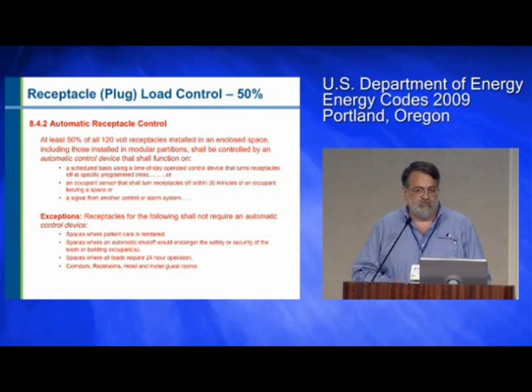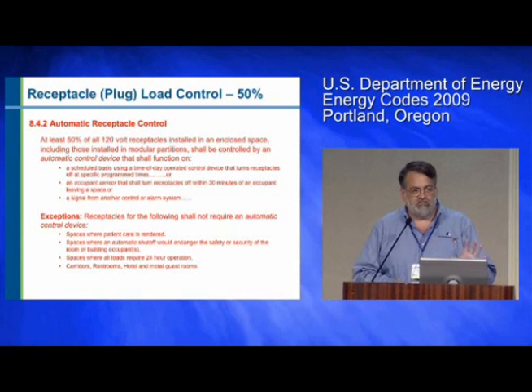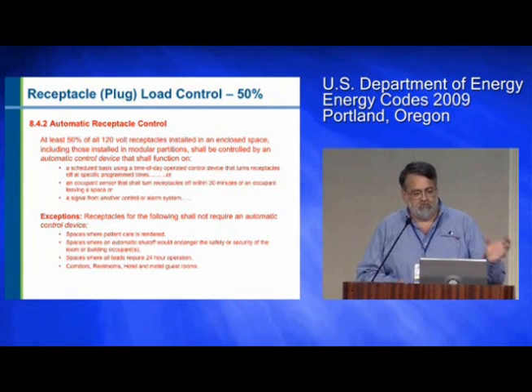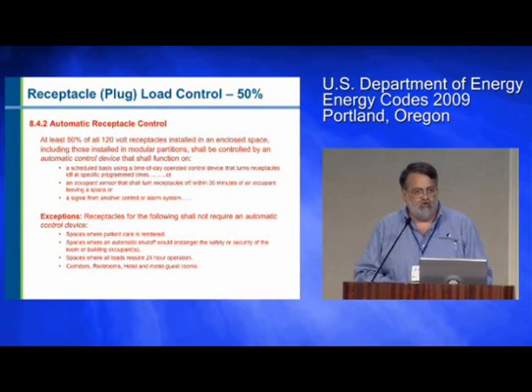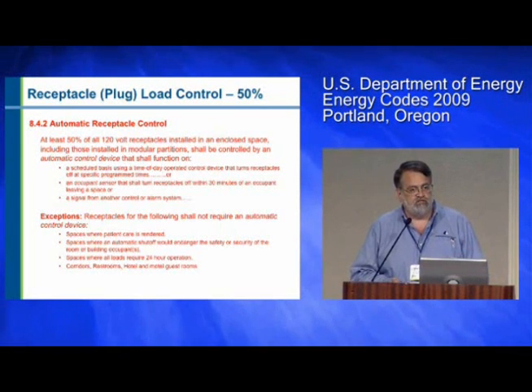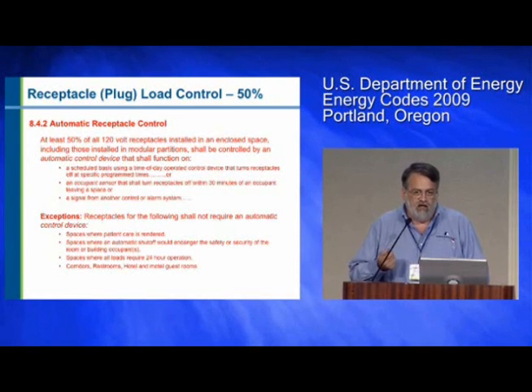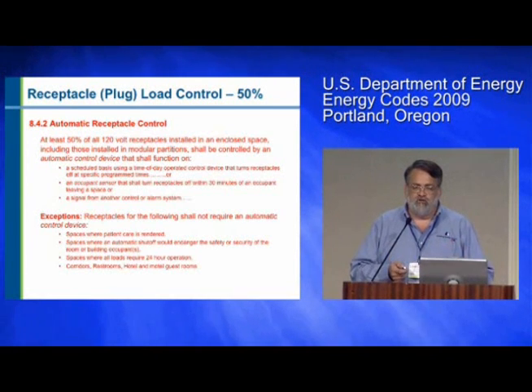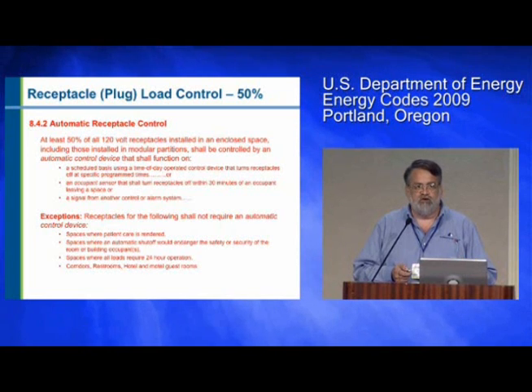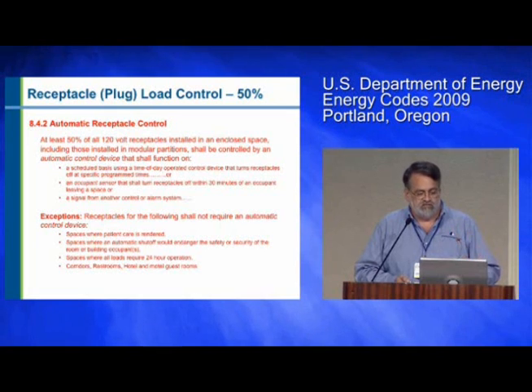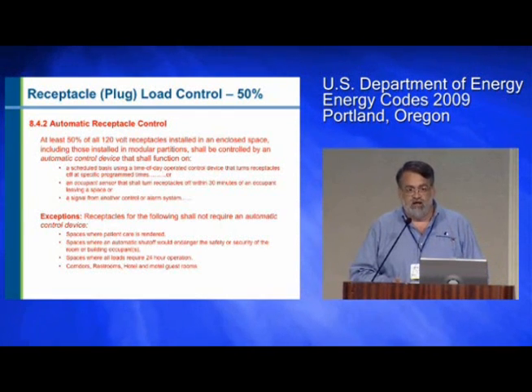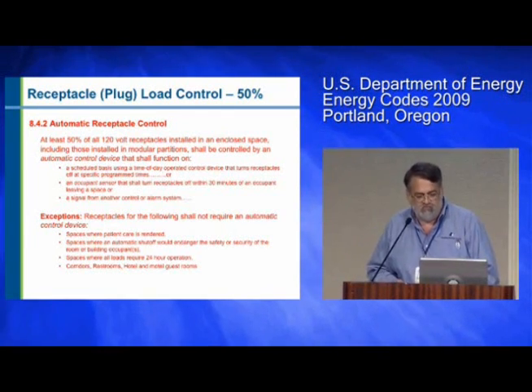How you pick the 50% is left up to the designer. That gives a lot of flexibility. You can put them all over in one place. You could put them half and half, a top and a lower one. That's left up to the designer. There are some exceptions, some places where it just doesn't make sense or might be dangerous to have a controlled receptacle, and those are listed as exceptions. The other plug load receptacle proposal that was considered was a way that limits how much load you can have in a receptacle, and at least the subcommittee decided for now that was just not practical and would never fly through the process.